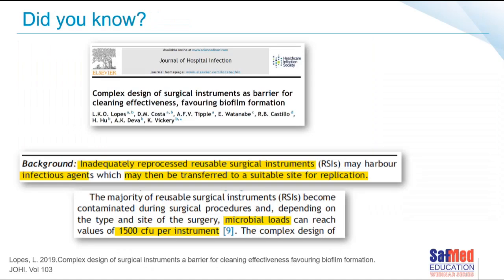Referring back to a published paper discussed in webinar one about complex instrument design as a barrier to cleaning effectiveness, the researchers told us the microbial load on an instrument used during a surgical procedure can be as high as 1,500 colony forming units per instrument. Those microorganisms need to be dealt with, and one of the ways we do that as part of the cleaning process is to subject them to thermal disinfection.